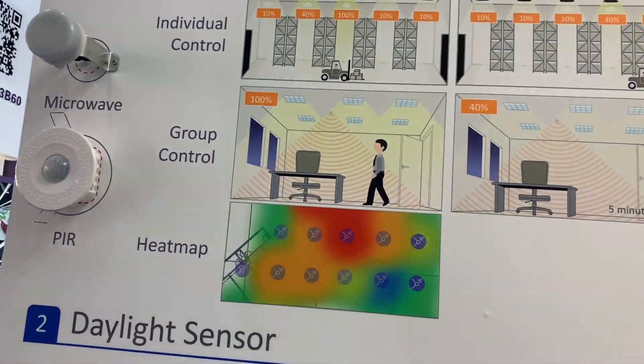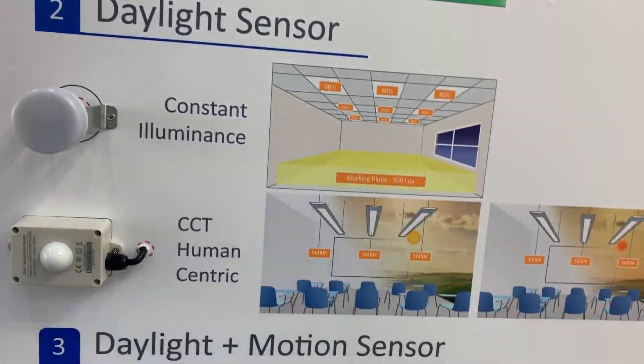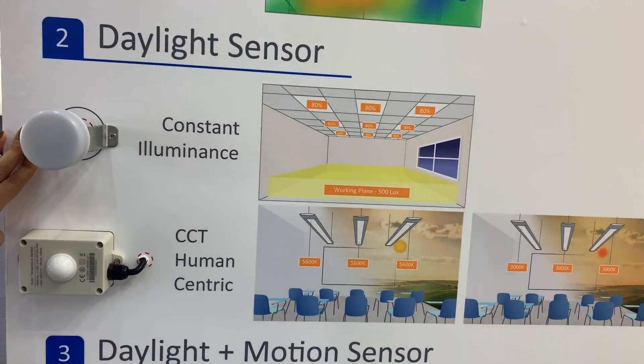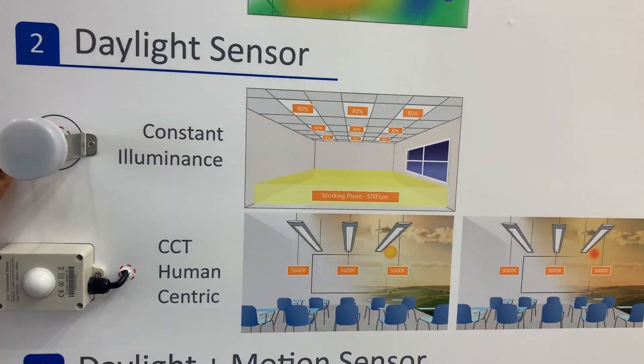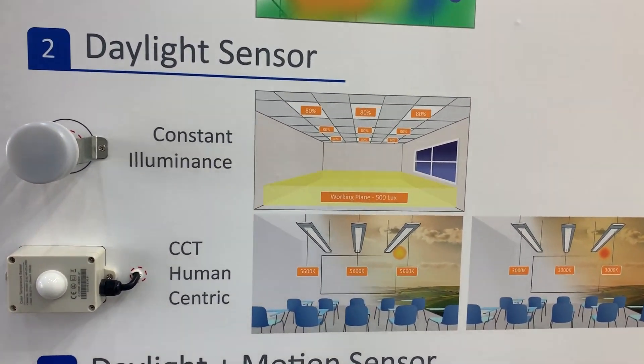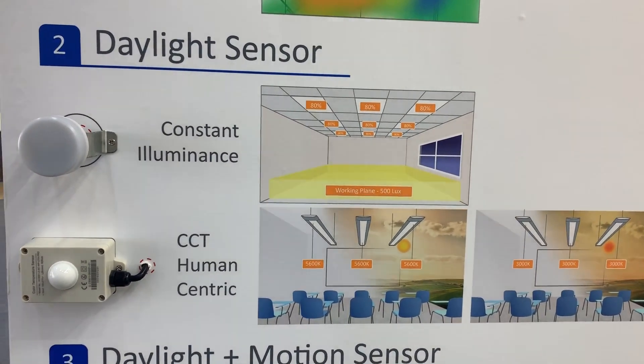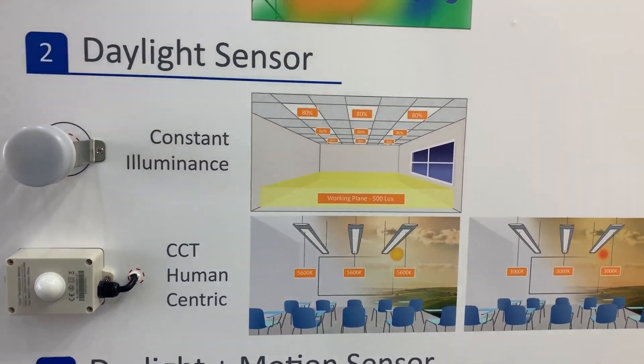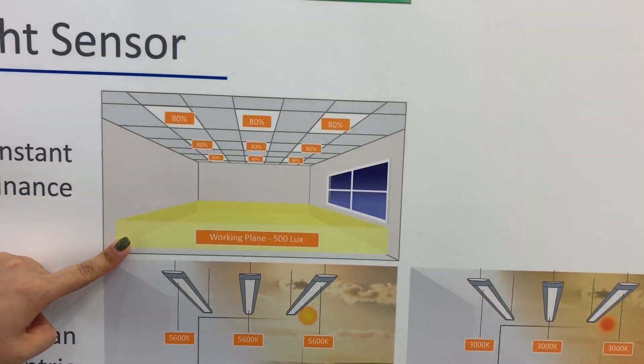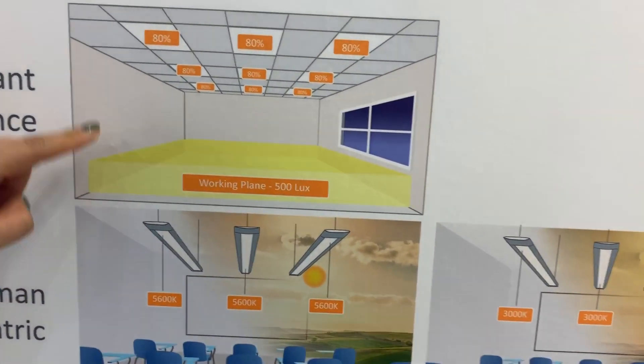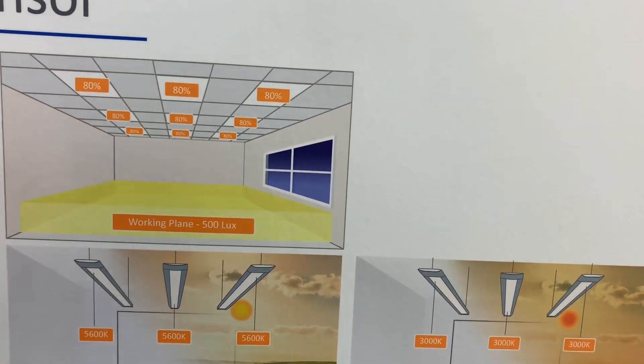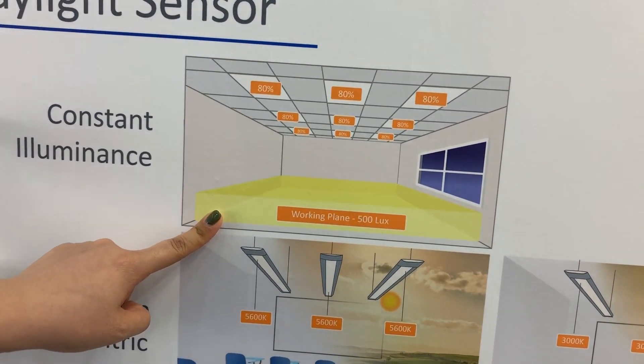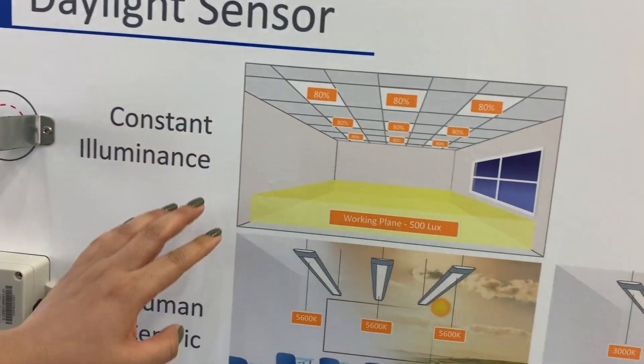I would also like to introduce the daylight sensor. This is a constant illuminance daylight sensor, which is ideal for industrial applications where there are skylights or other sources of natural light. You can set a working target of, for example, 500 lux, and all lamps bound to the sensor will maintain that 500 lux level automatically.